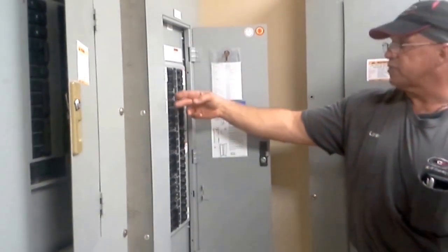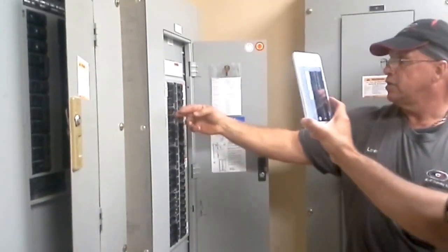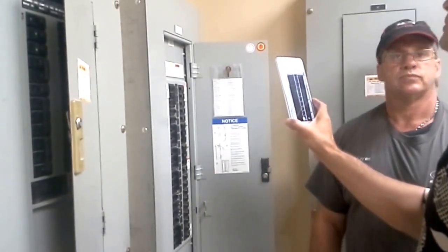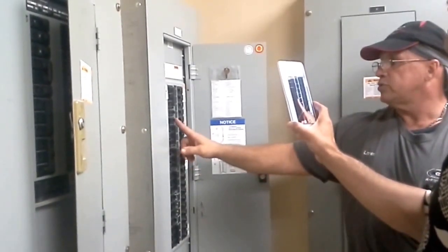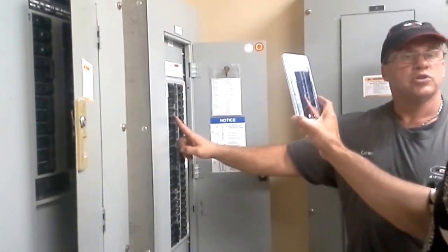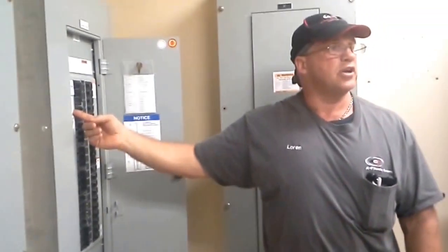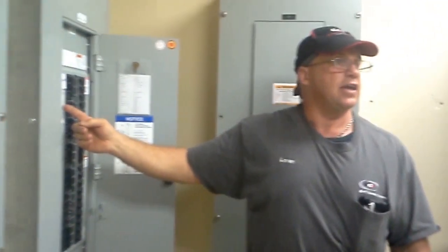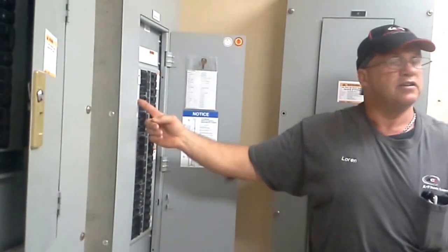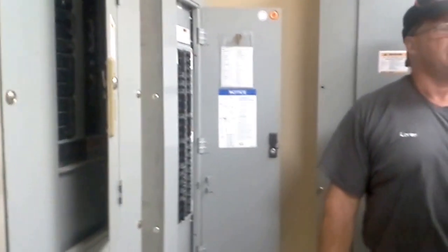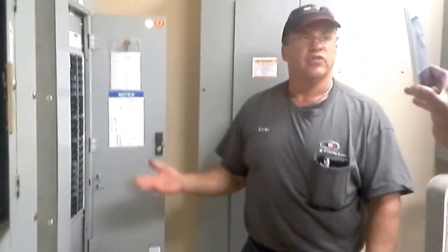They are on 2 separate circuits because if one fails, it's not going to trip the other one out. I have a lot of problems where sooner or later the coolant heater usually goes out first. That trips out. If it's on the same circuit, it'll trip your battery charger out, and in one day your battery will be dead because you have a digital controller out there, and you'll never know it because your annunciator will also go dead, and you will have no alarm.